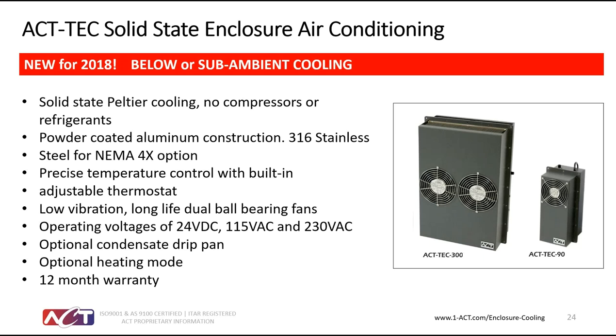Some applications just can't take a lot of vibration. If you have a high-end measurement value that you're taking, some of these devices can't take the vibration of a compressor motor going on and off. It actually causes errors in the measurement of certain types of applications, especially in medical or military. And there is an optional heating mode with this device, so it can go from cooling the cabinet to heating the cabinet, depending upon your application.